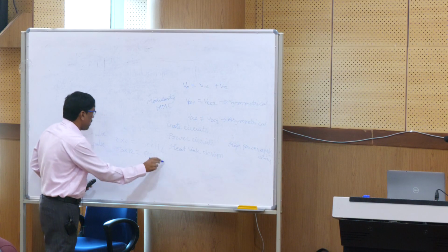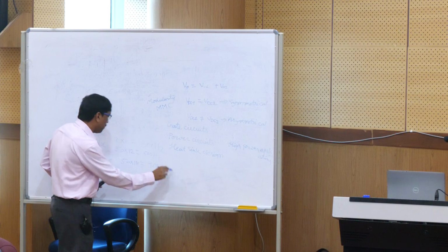Now if you make use of the 12-pulse rectifier, what is the frequency? Yes, 600 Hz. And then 18-pulse, 50 into 18, how much? 900. Or the maximum that we can go for is 24-pulse rectifiers. That will be 50 into 24, how much will you get?